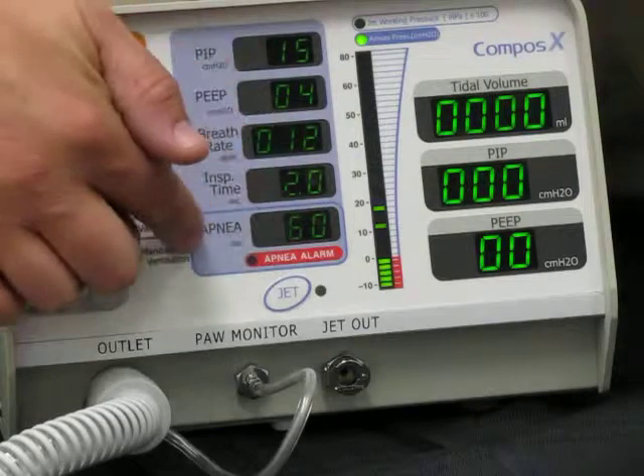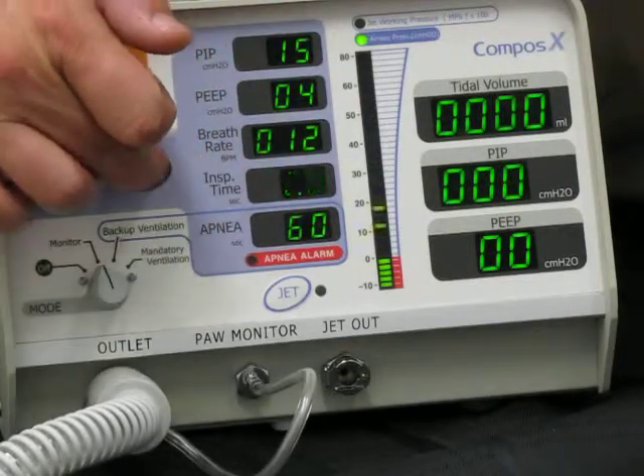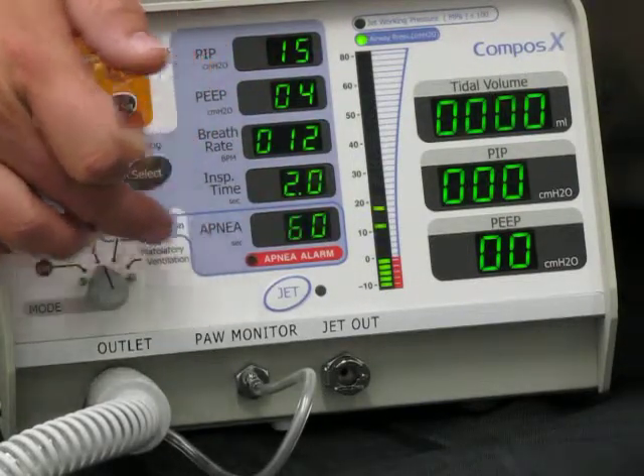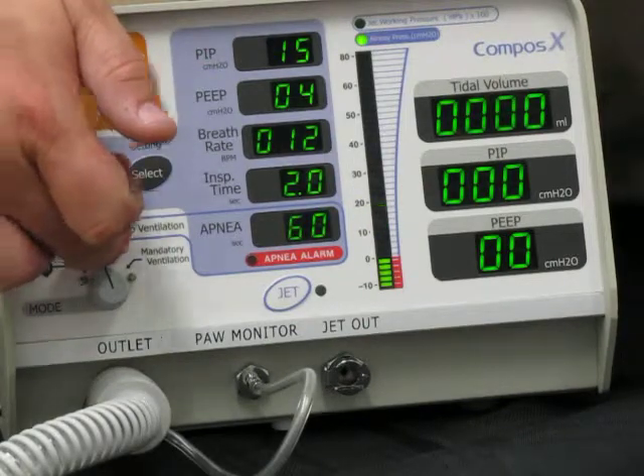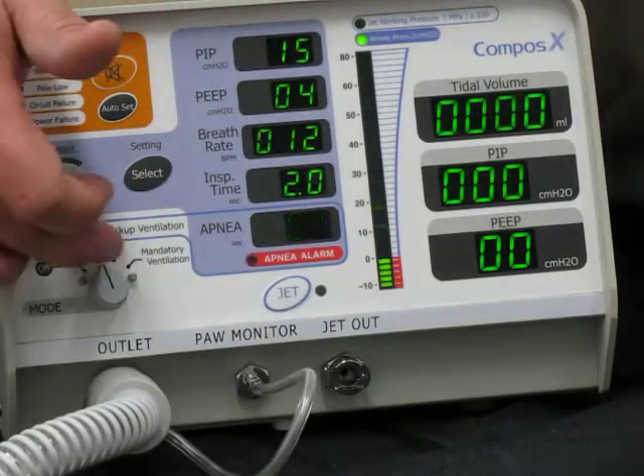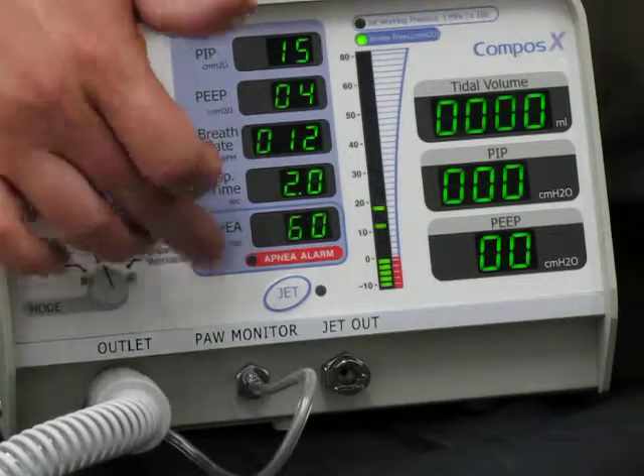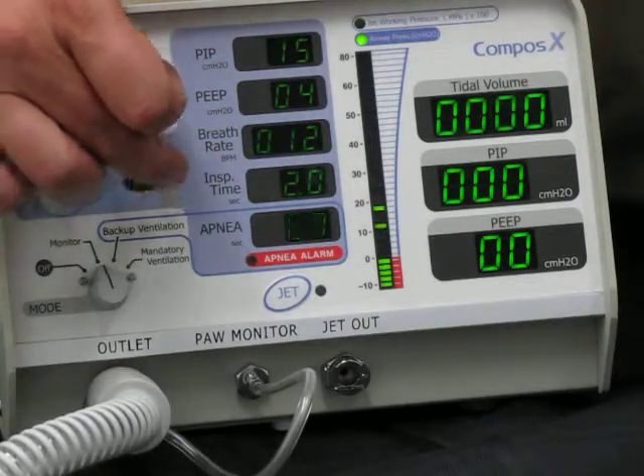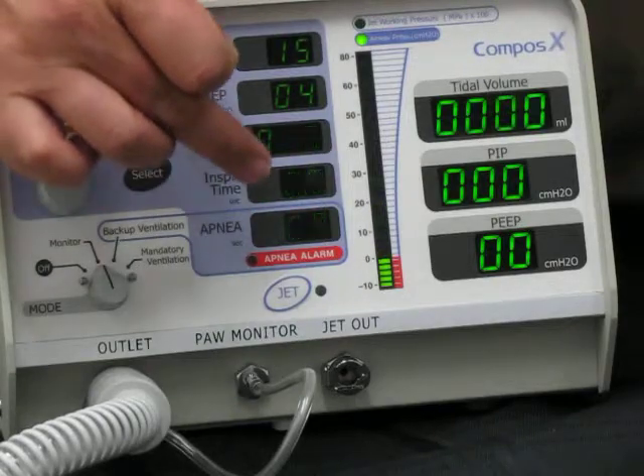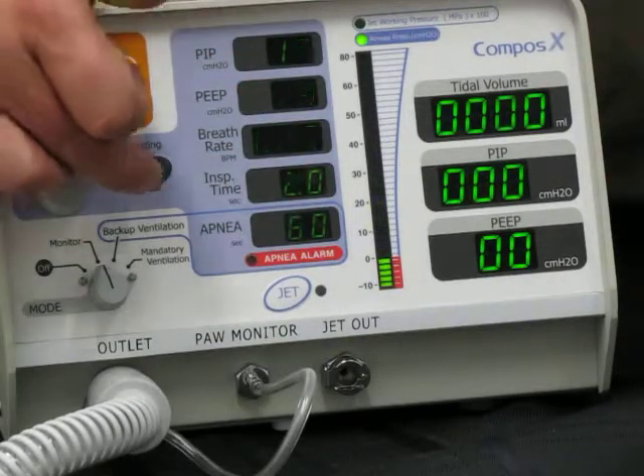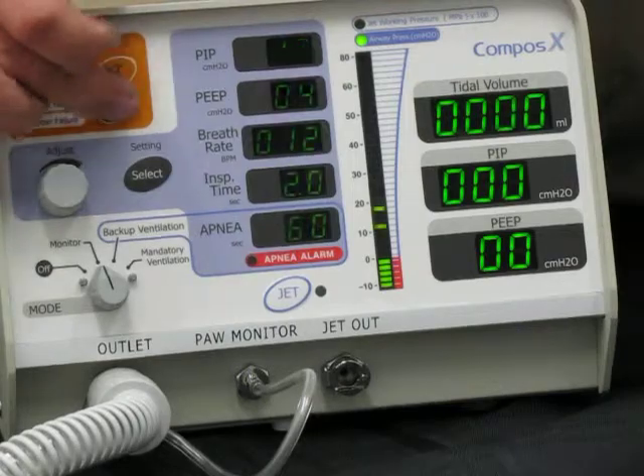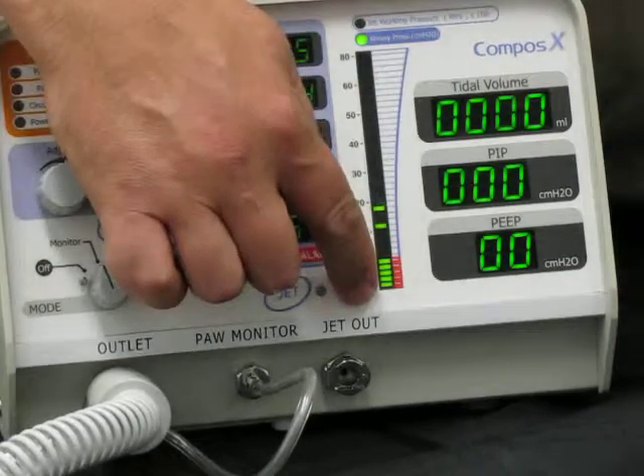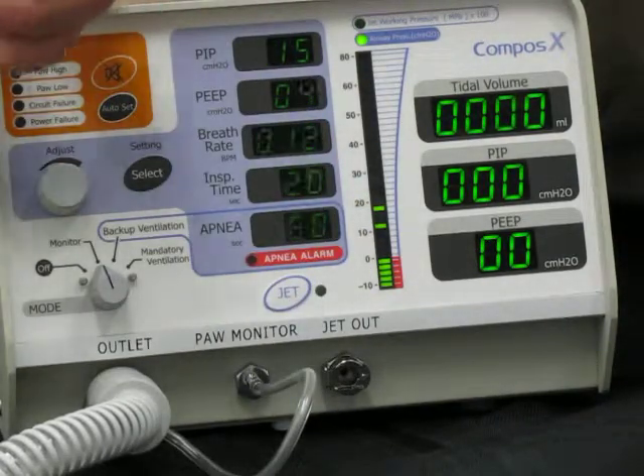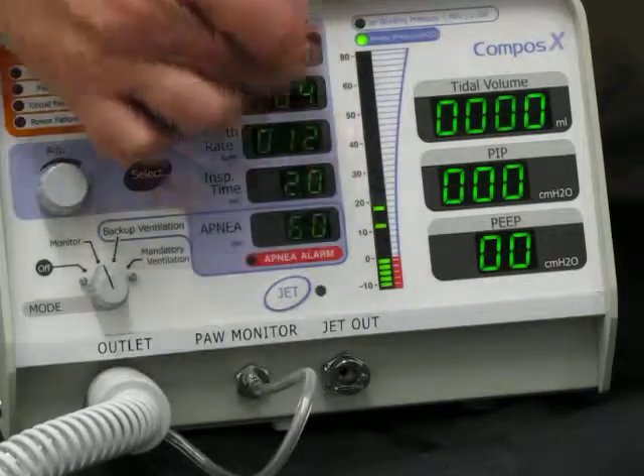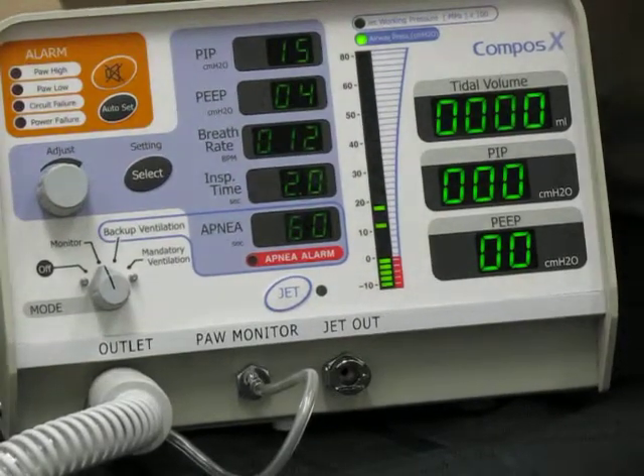Then the last setting is apnea down here. And with apnea, that will only be used in backup ventilation mode, but you can set that to 0 to 60 seconds. And in backup ventilation mode, if the animal stops breathing, the unit will automatically turn on and alarm and start breathing for the patient. Anytime we do all those settings, we want to hit auto select to stop that beeping, and then the system will kick into those settings. What we're going to do is then we're set to attach the patient.